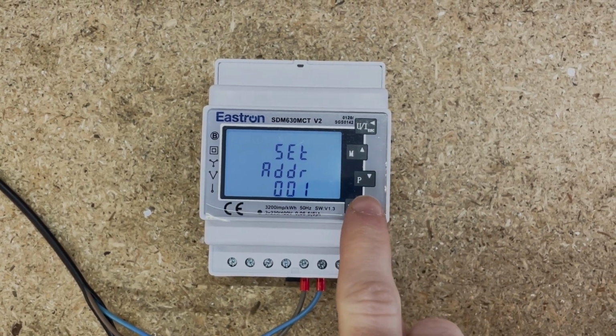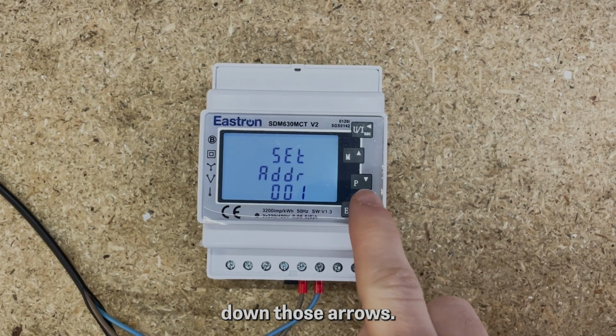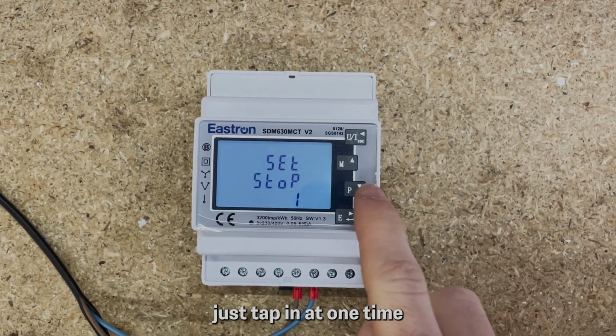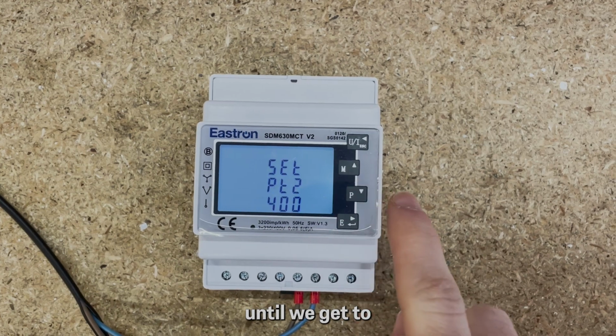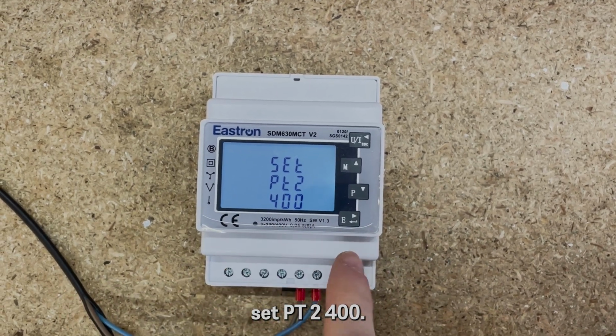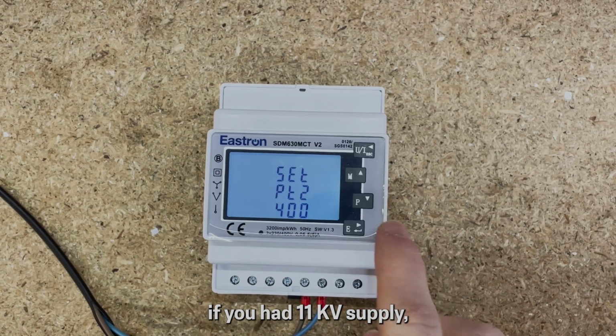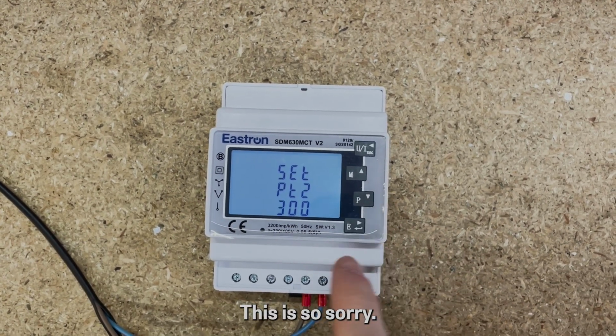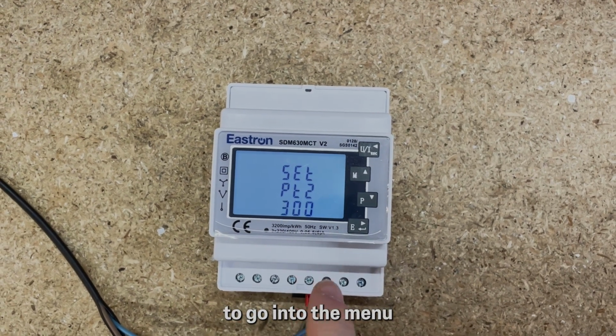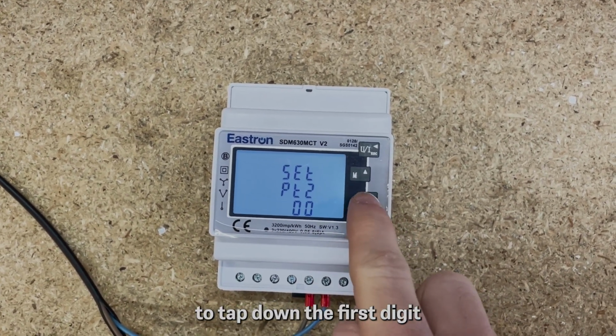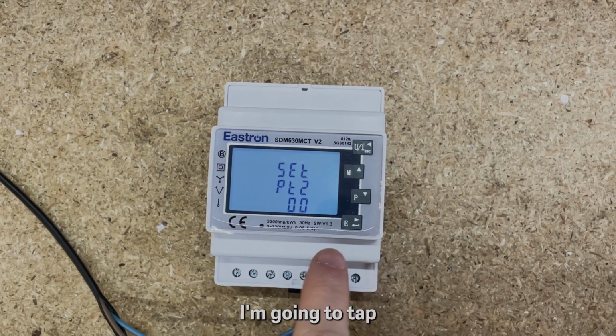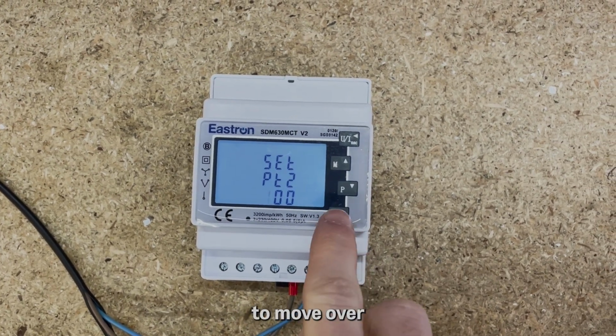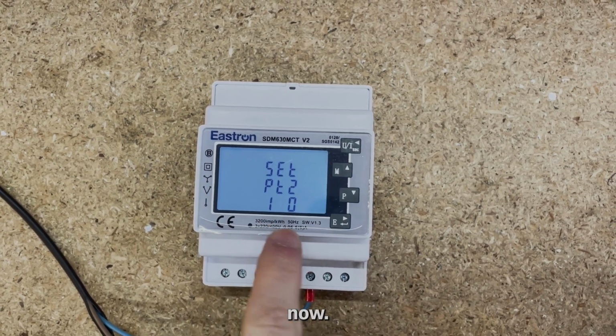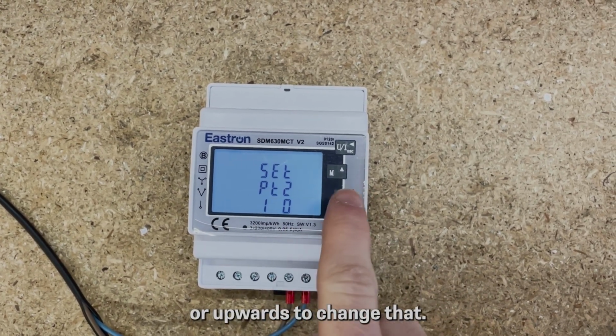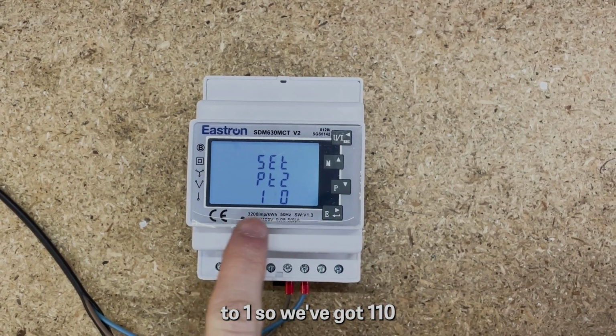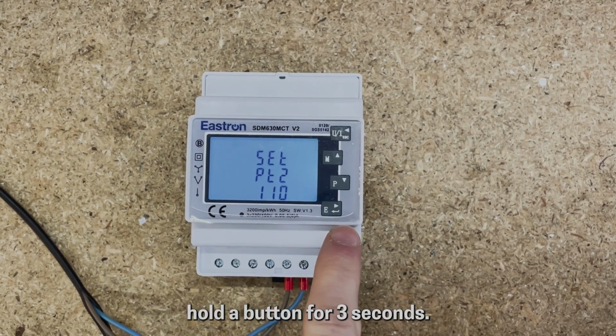We're going to tap the P button to scroll. This is a downwards arrow, so we're going to scroll through the meter, just tapping it one time until we get to set PT2 400. So for example, if you had an 11 kV supply, we want to change this. I press and hold the E button to go into the menu, and now I'm just pressing the P button to tap down the first digit to 100. I'm going to tap the E button once. Don't press and hold, just tap to move over to the next digit. You see that's flashing now. And we're going to use the M or upwards arrow to change that to 1. So we've got 110. Then to lock that in, we'd press and hold the E button for 3 seconds.